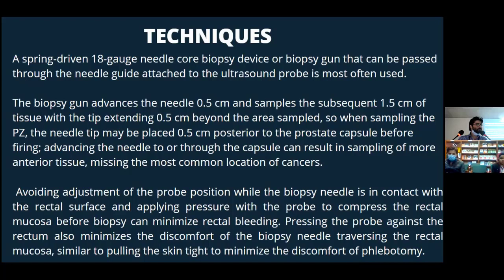For instance, at this time, we have the biopsy gun, and since it is spring loaded, you can't have different kinds of pressures or forces applied by different people. So it is the same pressure whether you apply or I apply or somebody else who is an expert applies. So now everything is standardized.